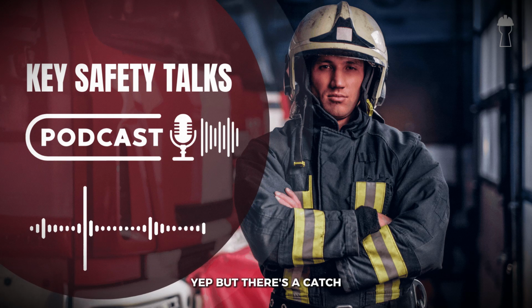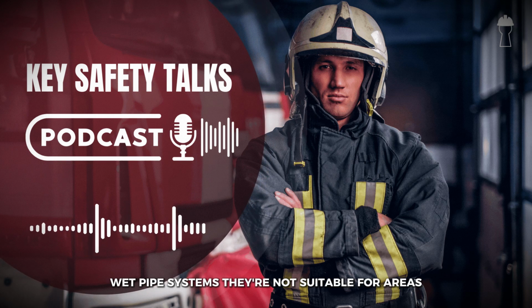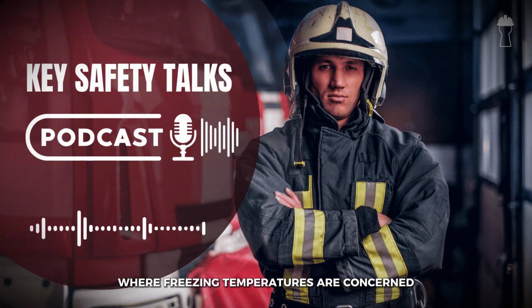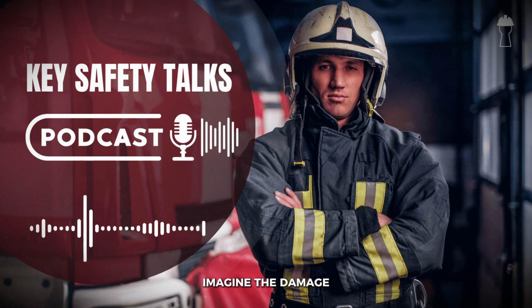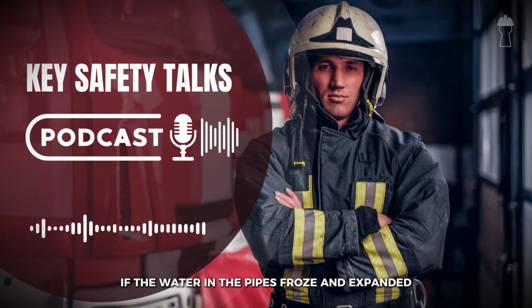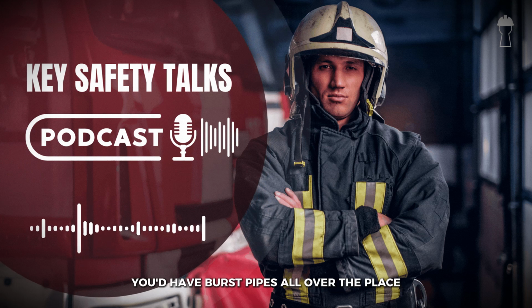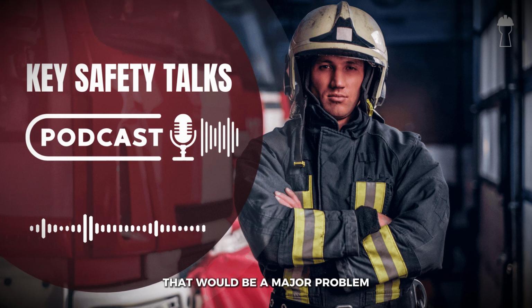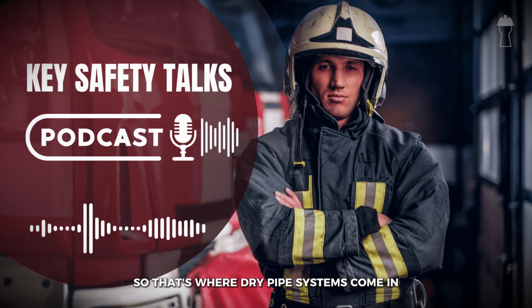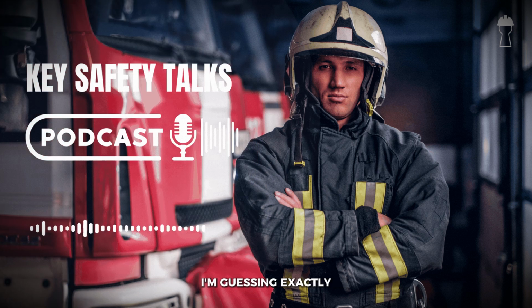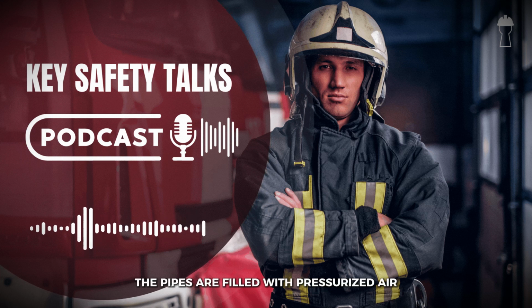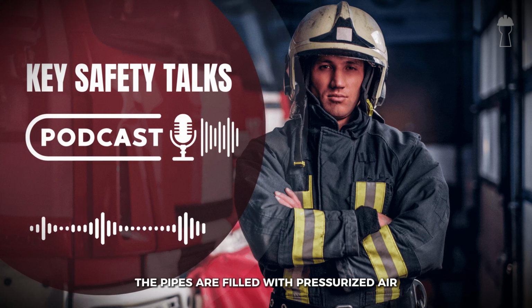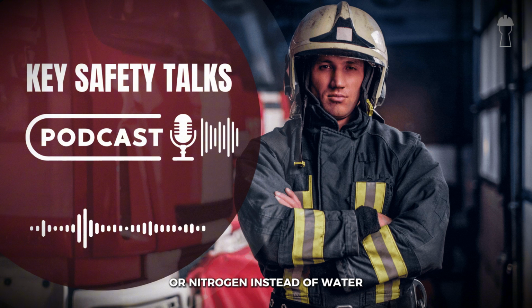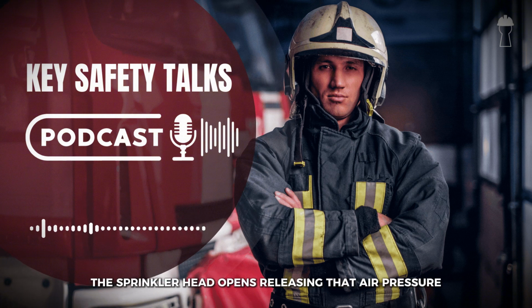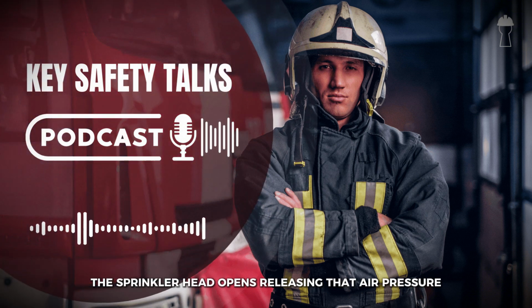Yep. But there's a catch. Wet pipe systems are not suitable for areas where freezing temperatures are a concern. Imagine the damage if the water in the pipes froze and expanded. You'd have burst pipes all over the place. Oh, yeah, that would be a major problem. So that's where dry pipe systems come in, I'm guessing. Exactly. In a dry pipe system, the pipes are filled with pressurized air or nitrogen instead of water. And when a fire is detected, the sprinkler head opens, releasing that air pressure.